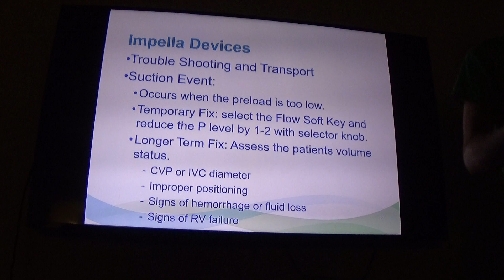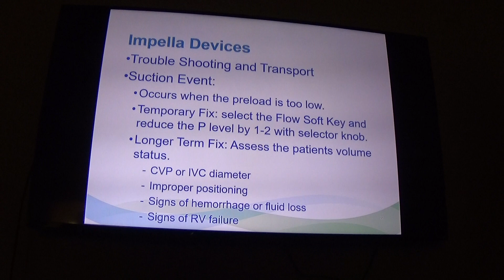Signs of right ventricular failure, if that's the case, unfortunately it's one of those this is really bad, because now they have biventricular failure and things are getting really bad at this point. And again, then you're talking about, well, does this person need epoprostenol or another kind of something to help that right ventricle. So next thing you might see is a lower than expected flow based on the device and P level. Like I was talking about, if you're seeing that the flow rate is not in that range for your expected P level based on the device, you may have a real high SVR, so be considerate of your vasopressor use.